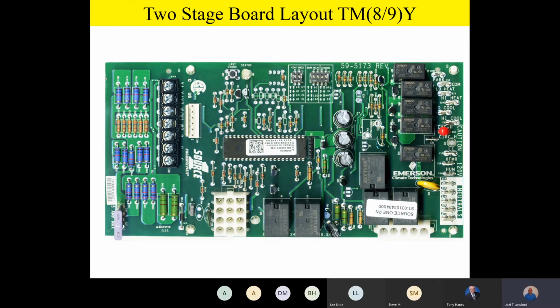So on a 2-stage board, this is a 2-stage gas heating and also 2-stage cooling capable board. And you're going to find this on a TMY series of furnace. Now the TM8Y, of course, is 80%, and the TM9Y, I think, gets up to about 96 or 97%. This is a great furnace. Again, very, very versatile. It will literally match up with anything in our inventory except the 21 SEER momentum and the 21 and 20 SEER momentum fully communicating only product.